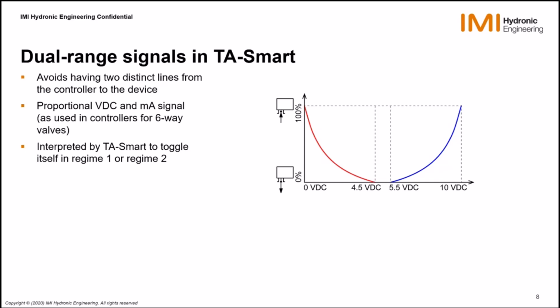So dual range signals in TA-Smart are very much the same as the ones that we have got in TA-Slider, with one exception. We have got milliampere dual range signals that have been added to TA-Smart, since TA-Smart has got milliampere analog input. So typically a dual range input signal is like this. If I am taking the 0-10 volt type of signal, we are exploiting the full 10 volt that we divide in three areas.